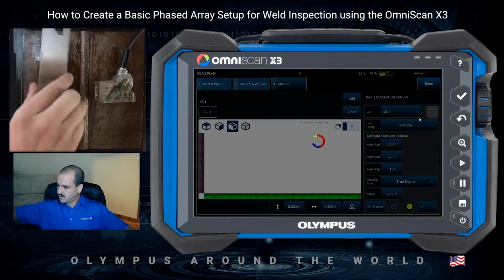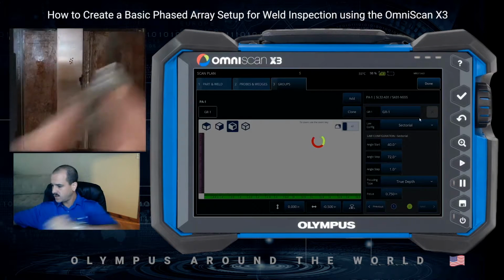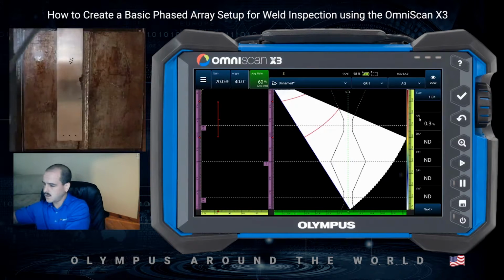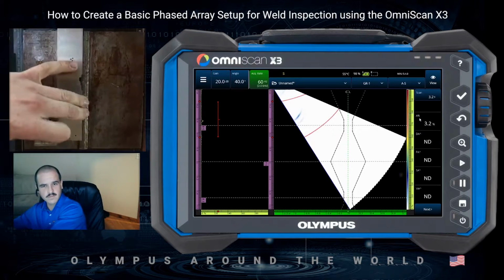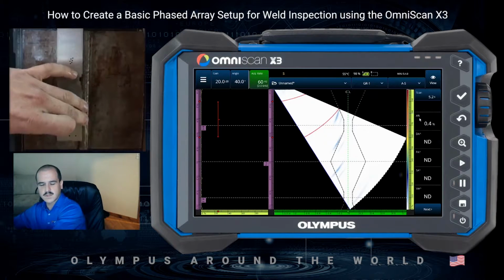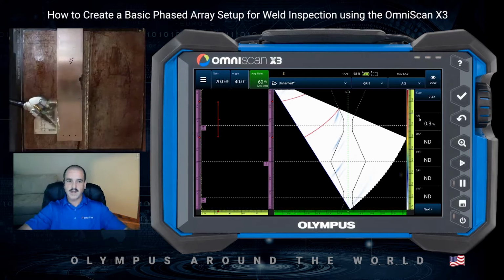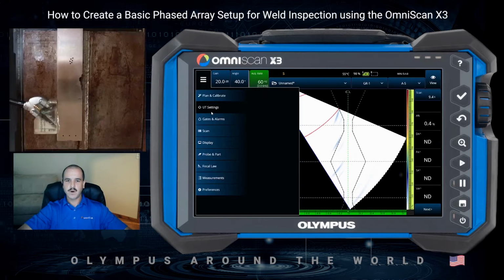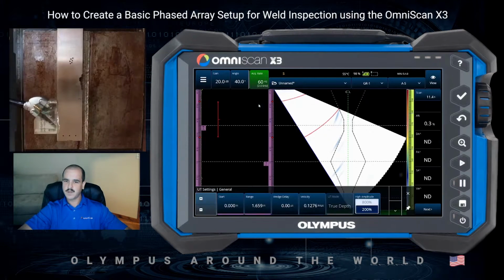And we'll pop a little calibration block up here. We'll utilize the side drilled holes for our calibration. So after navigating through the scan plan and configuring all that, we'll go into our UT settings and make a few slight adjustments. So our range is good. We got coverage of our root, plus the second leg, so we can leave that alone.